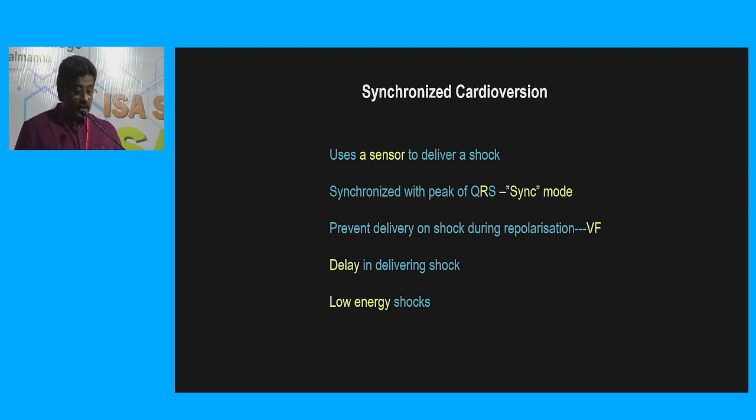Another thing you should know: when you are using cardioversion, there will always be a delay in delivering the shock. But with the defibrillator, it will deliver immediately. Why? Because here it is synchronizing.